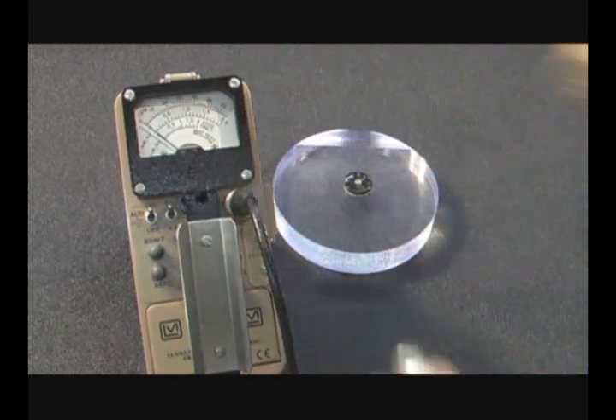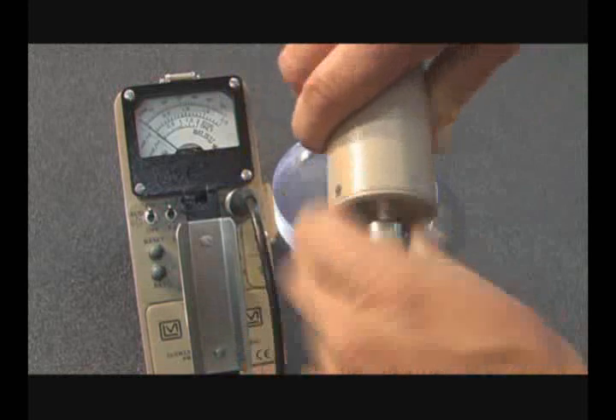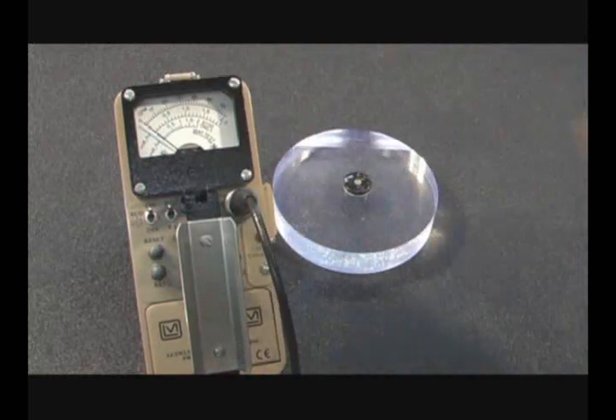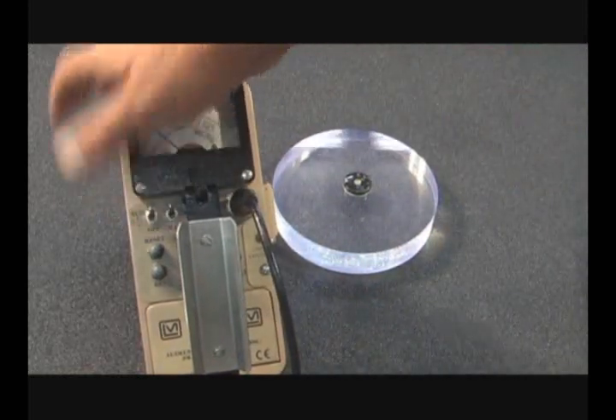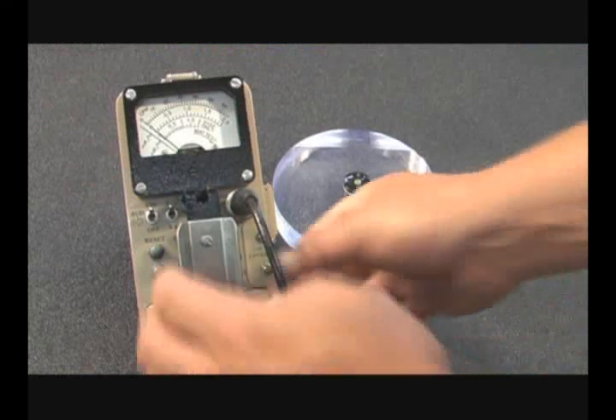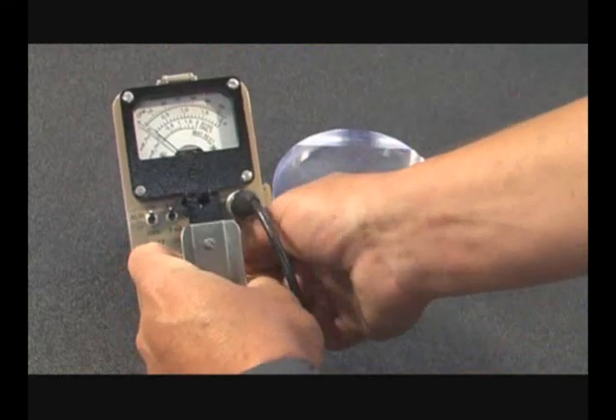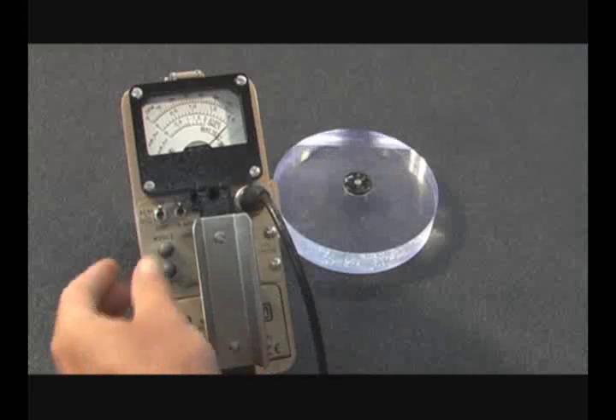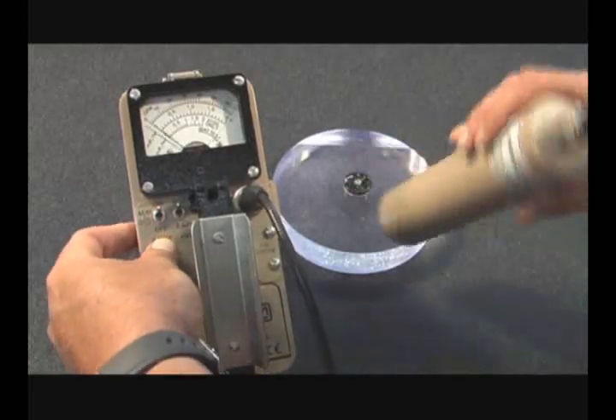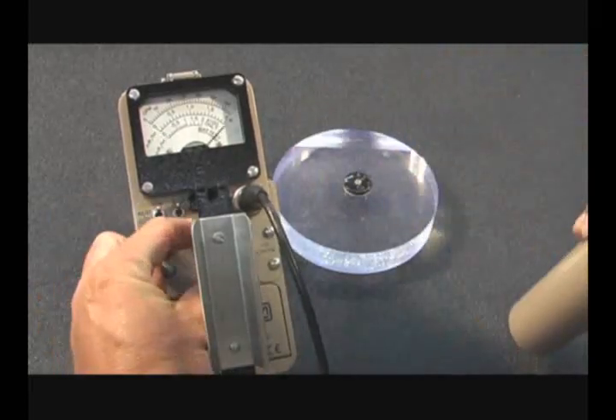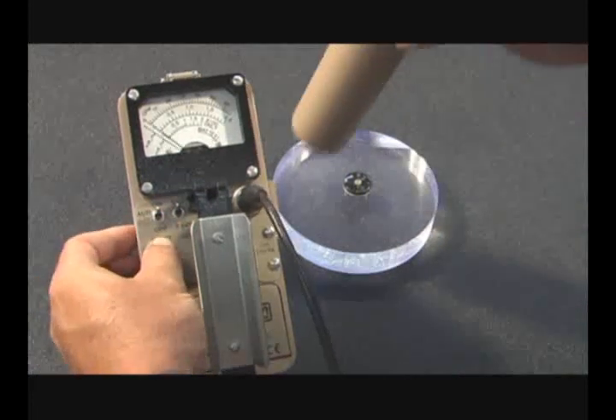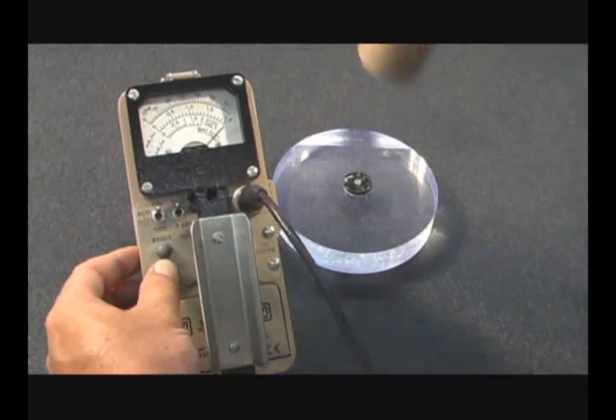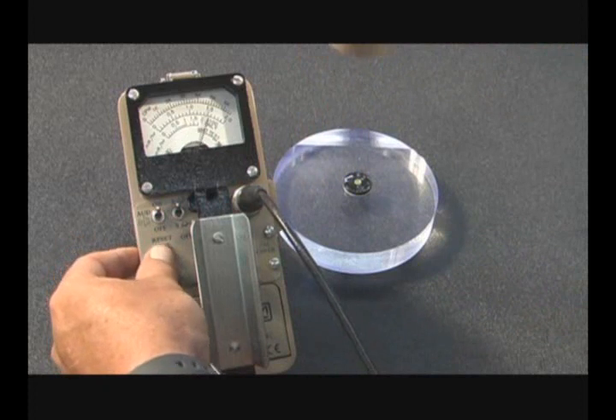Make sure that the audio switch on the Model 14C is in the on position. Turn the range multiplier switch to the times 0.1 position. The Model 44-2 is much more sensitive to small amounts of gamma radiation. Therefore, it can detect a gamma source from a further distance away than the Model 44-9 detector. It cannot, however, detect alpha or beta radiation.